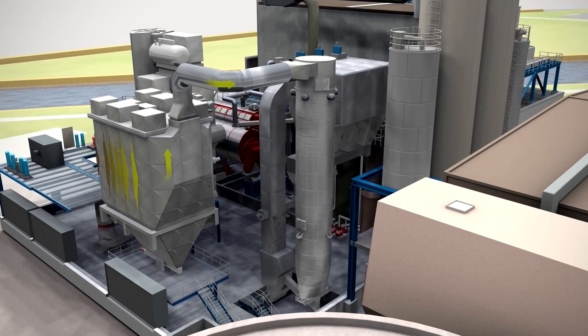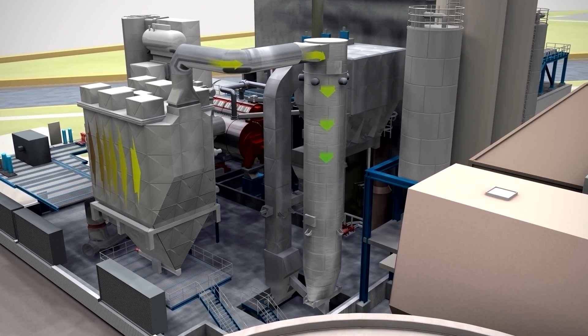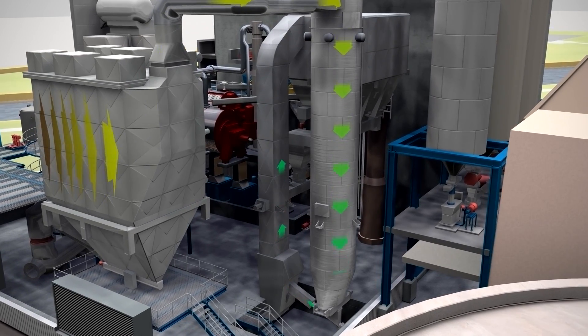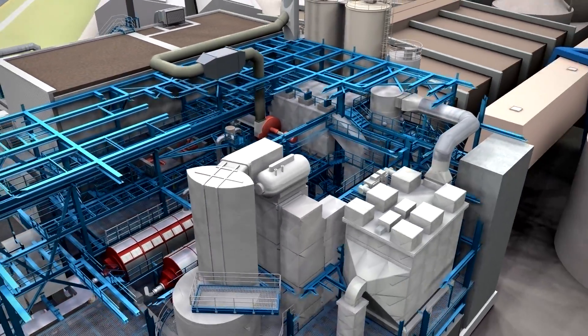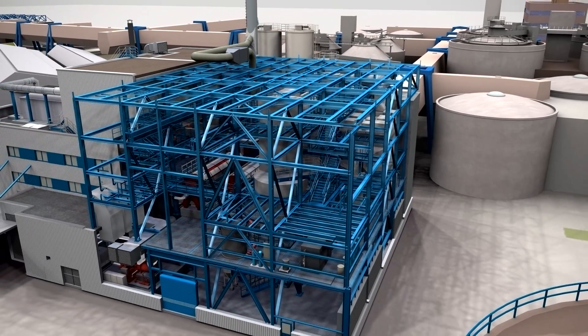A mixture of hydrated lime and activated carbon is added to help separate acidic flue gas components. The baghouse filter then separates the reacted lime, activated carbon and fine ash particles, with the de-dusted flue gas washed in a two-stage scrubber. The flue gas reaches a fan, then passes a silencer and leaves the end of the stack, purged and without any smell.